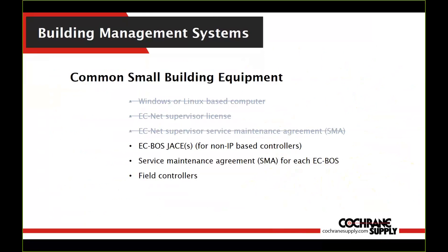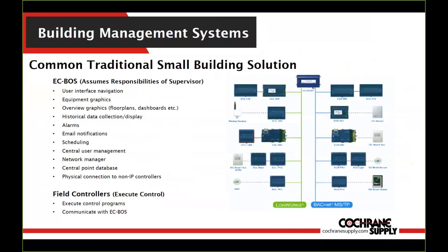In small buildings, typically due to cost or system requirements, we usually cut a lot of parts of that architecture out. We remove the Windows server, the supervisor, and that maintenance agreement. Maybe we'll keep an EC-BOS, especially if we have to integrate Lon, MS/TP, or any field bus that's not IP, and then field controllers to run your control. The EC-BOS would maintain all the function of your supervisor — navigation, graphics, historical data collection, alarms, email, scheduling, and user management. A common alternative is to just eliminate the EC-BOS and have a network of field controllers that can talk to each other, share some data, but with no visibility into the system at all.